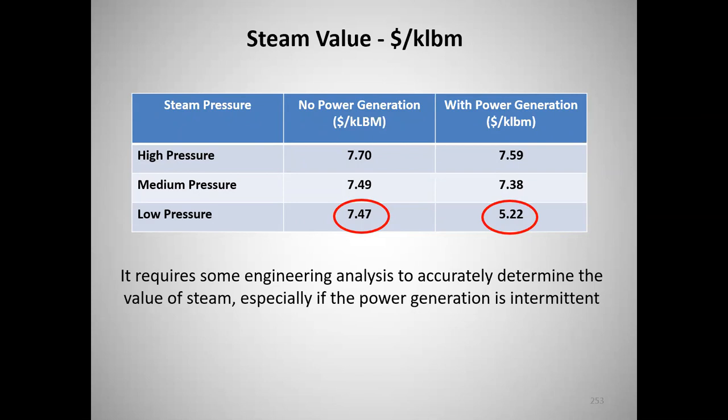And so it knows that providing 1,000 more pounds of high pressure steam costs this much money. Or you could reduce it; you can increase it or reduce it. It goes through each one of those, increases the high pressure, calculates the cost, then resets it to what it was before, then increases the medium pressure, goes through the algorithm, and likewise. These are not very easy to do by hand. People don't do these things by hand, but the computer software can do it easily.